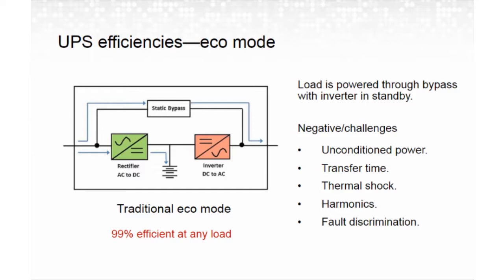And last is fault discrimination. Basically, under normal operation, the UPS uses the bypass to clear faults. So while you're in eco mode, it's difficult for the UPS to determine whether the voltage drop is a result of a fault downstream or a loss of power upstream. Sometimes you can see a UPS get stuck where it thinks the fault is actually a loss of power, and it transfers to inverter, and then it's got to take some extra time to realize it's not and clear it. All that can put people and equipment in danger because of extending the clearing time. So just some things you have to be aware of if you use eco mode.